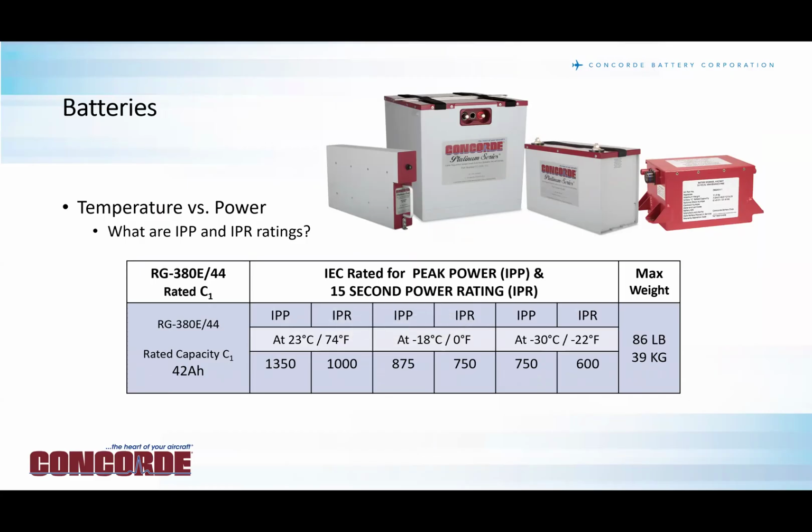Okay. Temperature versus power. What is IPP? Initial peak power. The current peak rating is basically like cold cranking amps, and we test that 15-second power rating under those temperatures. So think cold cranking amps, and you usually see this in ground power starting equipment specifications. So that would be helpful.